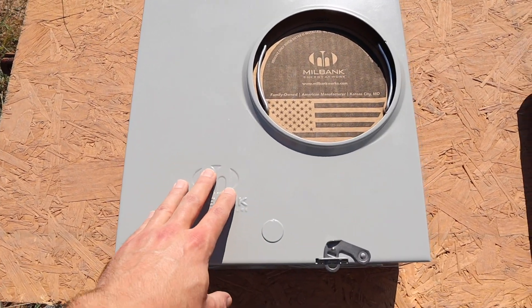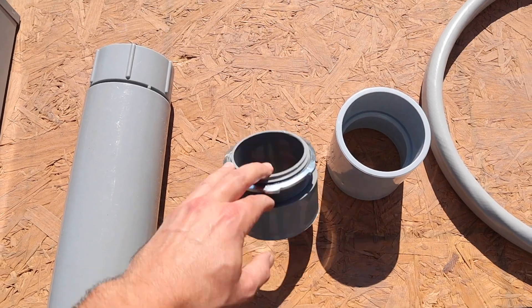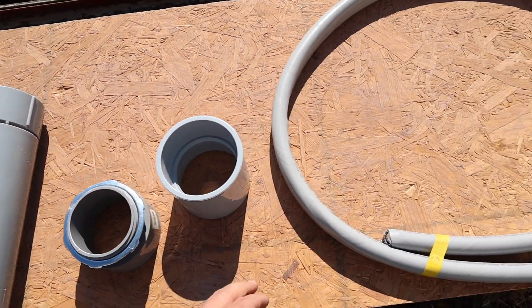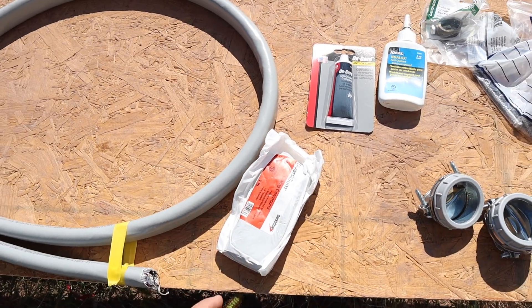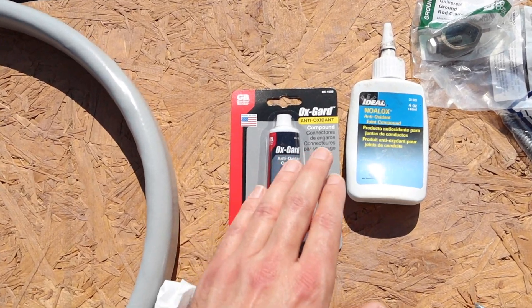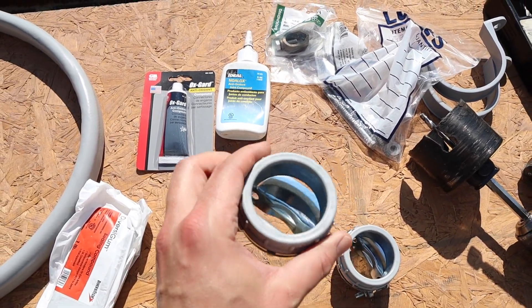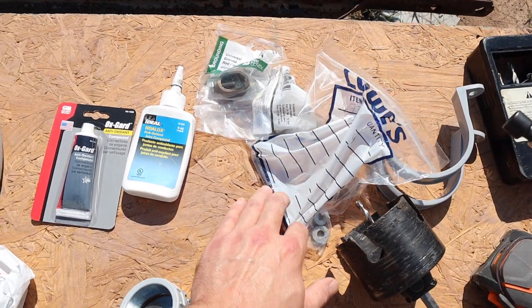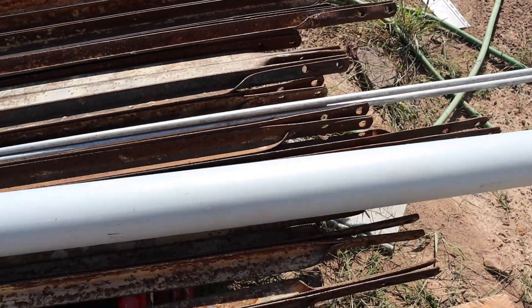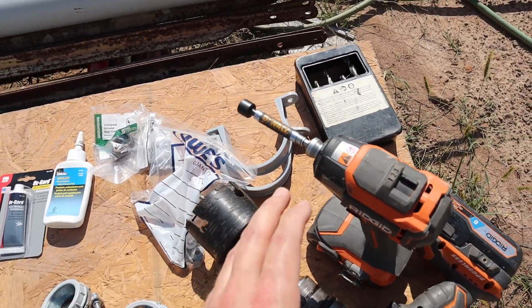Things I'll be using for my installation: this meter base, an expansion coupling which I'll show you how to install and what it's for, a three-inch coupling, SEU cable — that's 4-ought — duct seal to seal from the base to the inside of the house, Noalox for non-oxidizing properties, a two-inch clamp for holding the SEU cable, lag screws, grounding clamps for the ground rods, schedule 80 conduit that's three inch, a couple brackets to anchor everything to the house, and a tool bag.